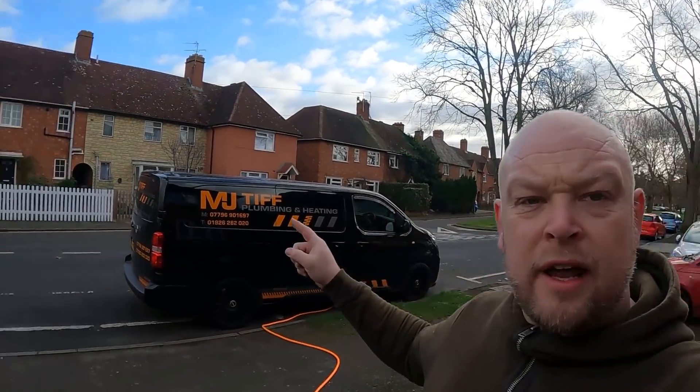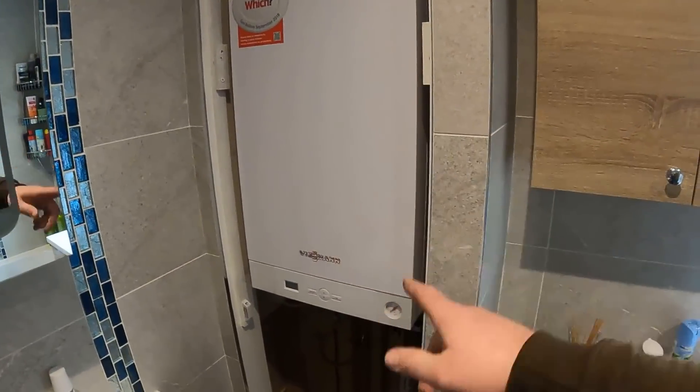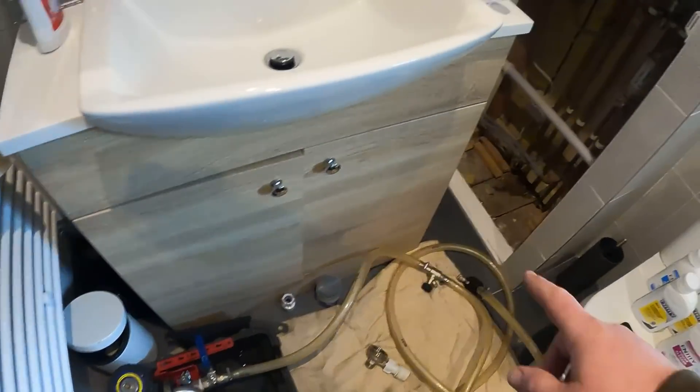It's always nice when you can park your van right outside the customer's house. We've just got here this morning waiting for the customer to leave. What we're doing is a full heating system flush. They've got a Viessmann boiler that's only been in two or three years, but they've been having a problem with hot water or heat inside. A service engineer came out, changed the heat exchanger, and advised them to get a system flush.